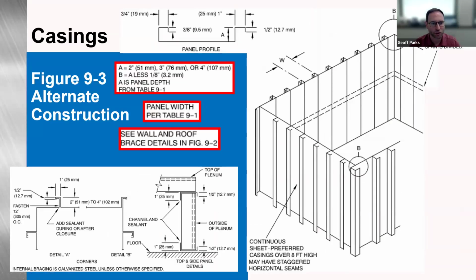Figure 9-3, the alternate construction. We're going to get into a little more detail on this one. This type of casing has tables that give you the gauges, what I'm calling the panel height, your A dimension, all based on the span and the pressure class you're looking at. This type of construction is for all sides and the roof. Your A dimension is the panel depth, your B dimension would be A less an eighth, and then you just lock them, you keep locking them in. The panel depth follows from table 9-1, which we're going to look at next.